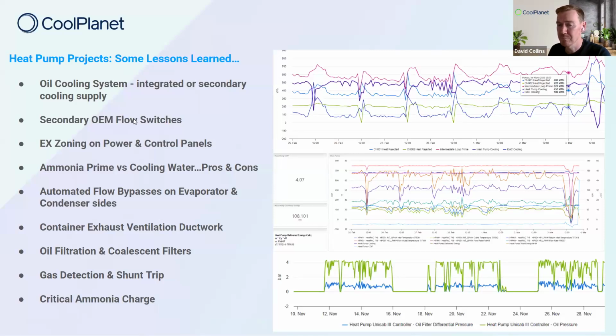Flow switches as well—you might be putting heat metering and electricity metering outside of the package itself, but having the OEM, the particular heat pump provider, integrate that flow switch back to the control panel is key. EX zoning within the container, between the control sections and the BMS sections of a heat pump panel, needs to be designed and specified to the correct standards.